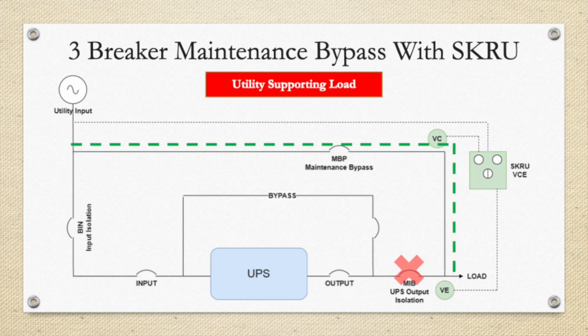If we go to the next drawing here, we're showing the 3-breaker maintenance bypass with SKRU running in maintenance bypass mode. So again, MIB is open, and BIN can be opened as well, so you can totally de-energize the UPS for any kind of repairs or maintenance while you're running on maintenance bypass. The bad part about a 3-breaker maintenance bypass is you've put all your eggs in one basket. Again, there's a single utility feed for both the UPS input and the maintenance bypass.